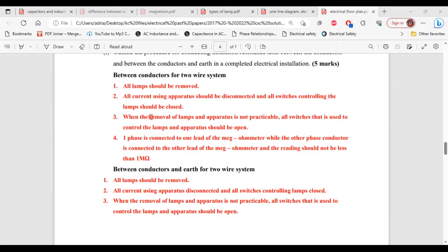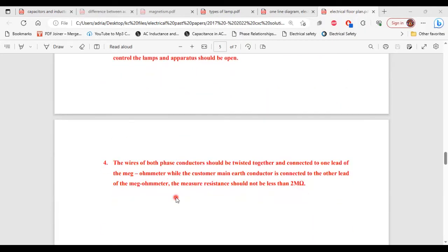Between conductors and earth for a two-wire system. 1 — all lamps should be removed. 2 — all current-using apparatus should be disconnected and all switches controlling lamps should be closed. 3 — when removal is not practicable, all switches controlling lamps and apparatus should be open. 4 — the wires of both phase conductors should be twisted together and connected to one lead of the megohm meter, while the main earth conductor is connected to the other lead. The measured resistance should not be less than two megohms.